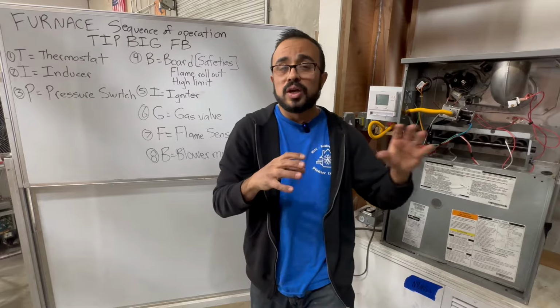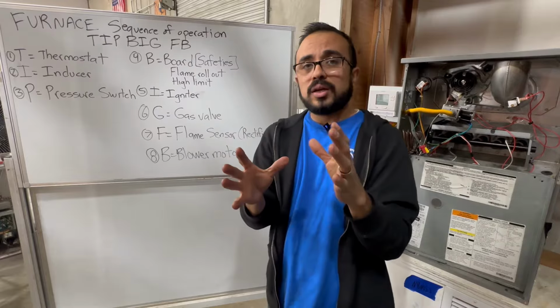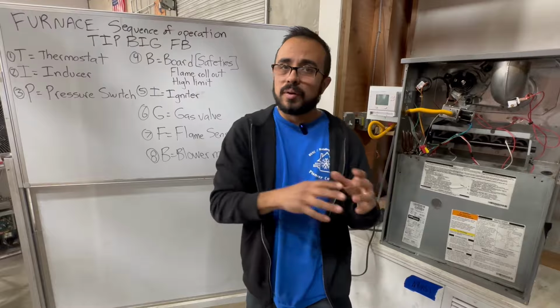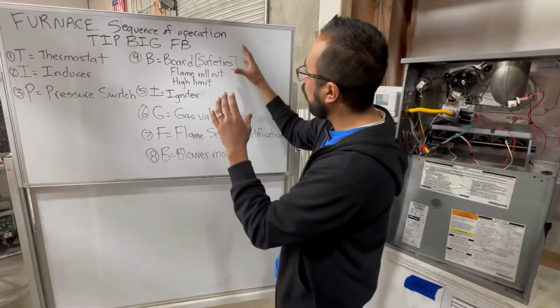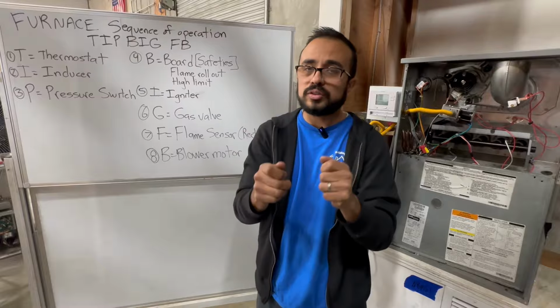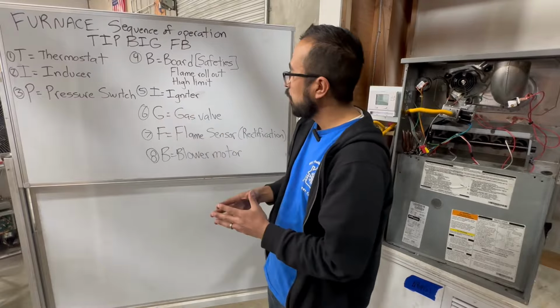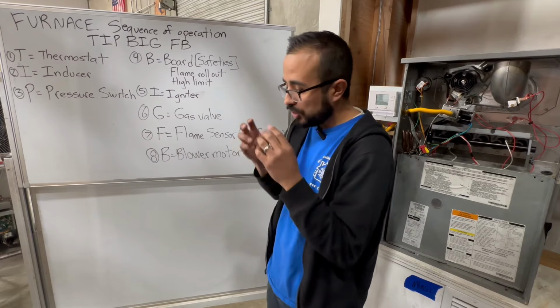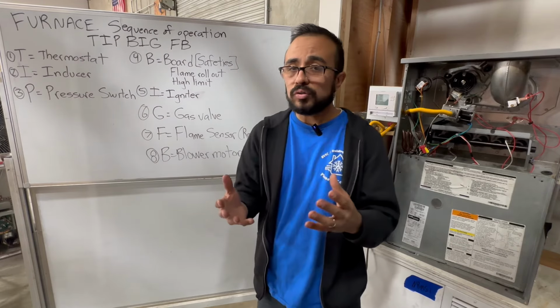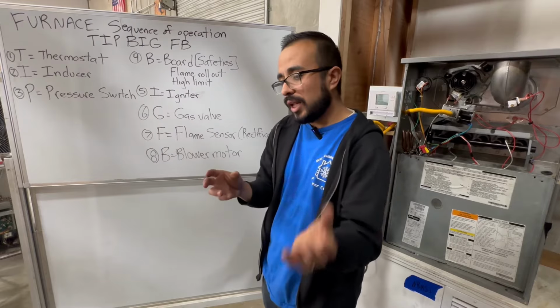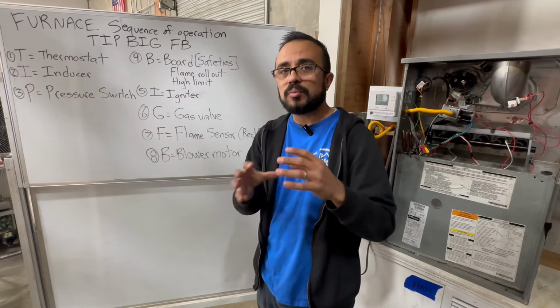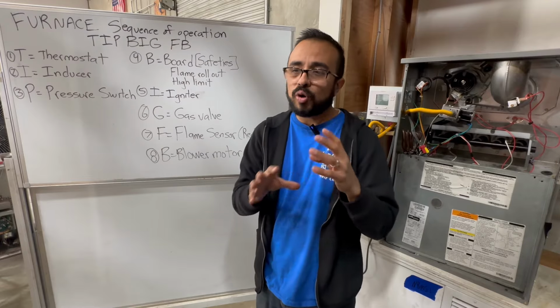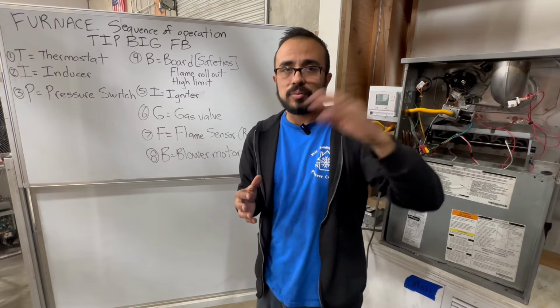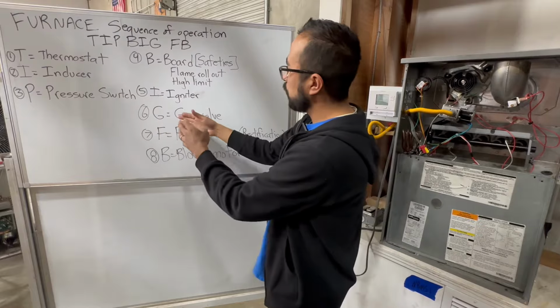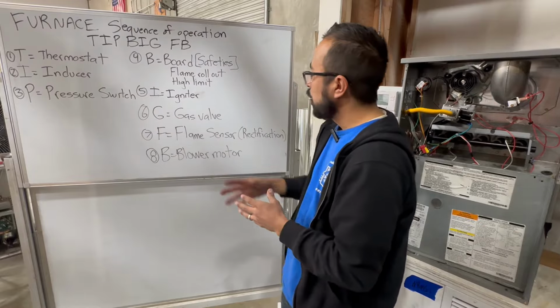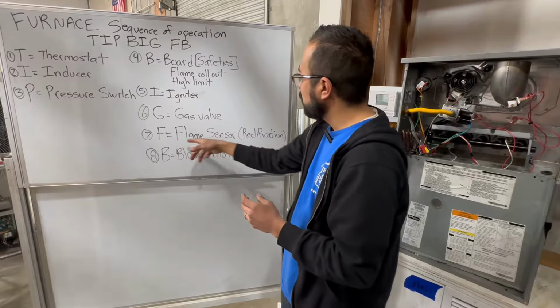So you want to ensure that on the furnace you're working on, you understand what's going on with the safeties. But at the end of the day, you just want to make sure that all safeties are closed. You should read continuity. And then your hot surface igniter receives 120 volts, turns cherry red. Your gas valve receives 24 volts. You were able to see how we were able to check the inlet pressure and the outlet pressure. You're looking in between 8 to 11, more or less, from the inlet pressure coming from the city. And then once it receives 24 volts, about 3.5 coming out, your flame sensor is going to detect that flame.